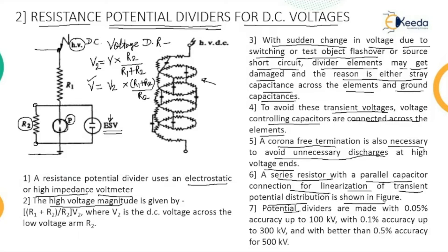The range of this potential divider with 0.05% accuracy is up to 100 kilovolts — meaning the voltage drop may be 0.05% of 100 kV. With 0.1% accuracy, voltage measurement is up to 300 kV using this electrostatic voltmeter. With 0.5% accuracy, measurement is possible up to 500 kV.